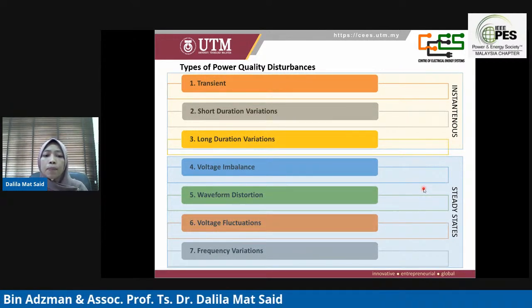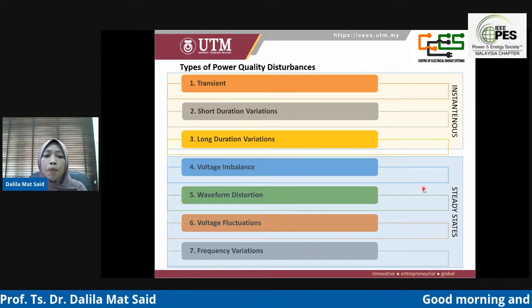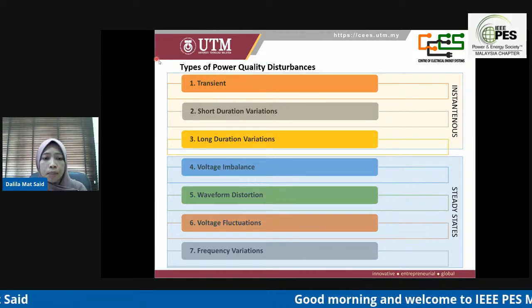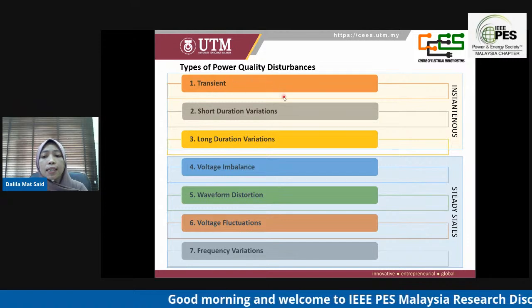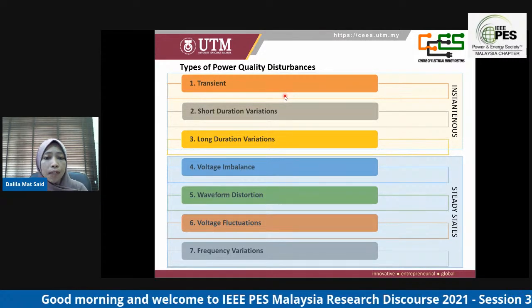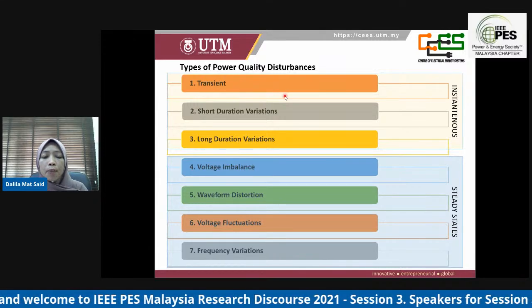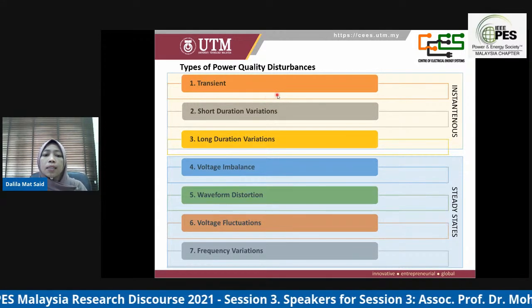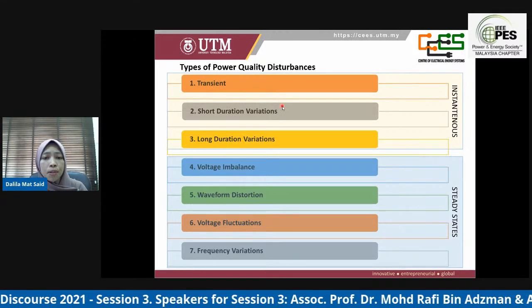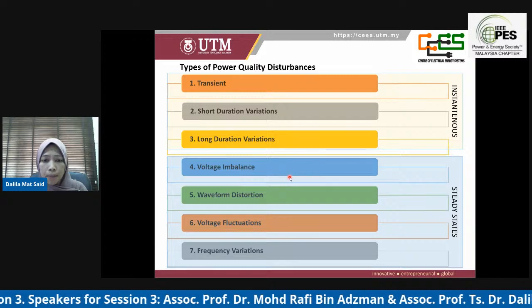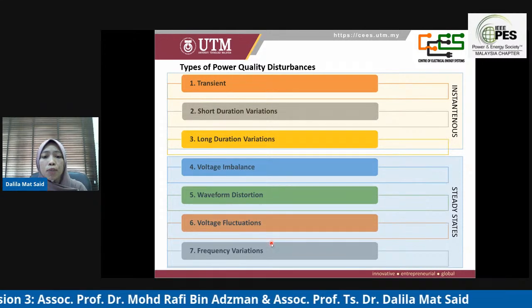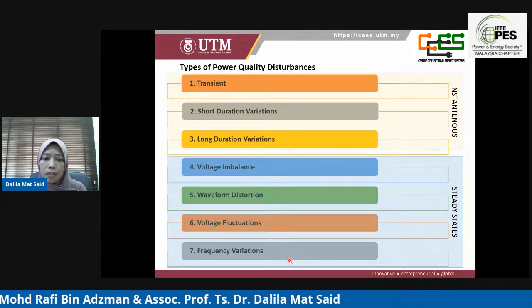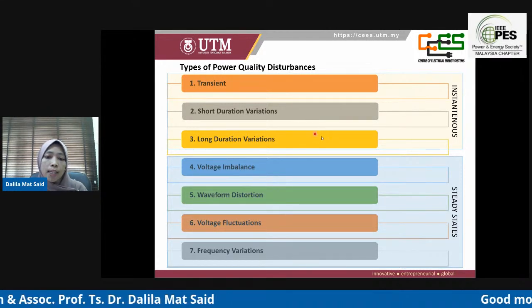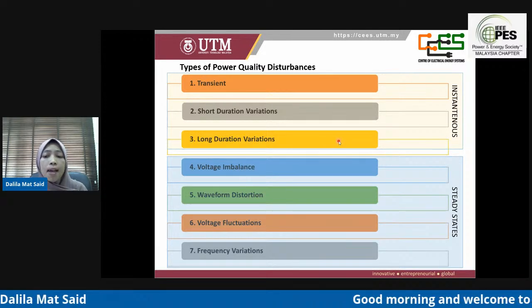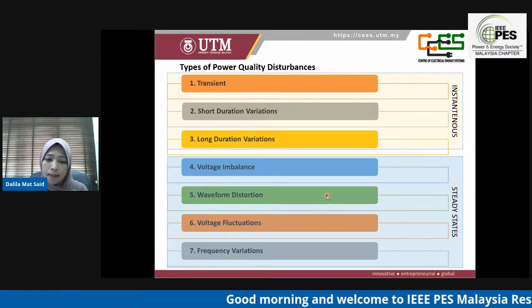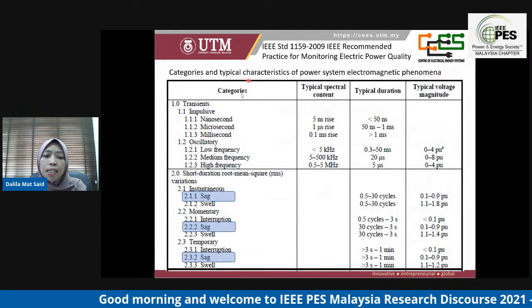So refer back to IEEE. From the list, IEEE provides a comprehensive summary on the types and classes of the disturbances that can affect the electrical power, which can be simplified by dividing them into 7 types of disturbance, starting with the transient, short duration variation, long duration variation, voltage unbalance, waveform distortion, voltage fluctuation, and frequency variation, where the first 3 types we can categorize as instantaneous and the remaining 4 as the steady state.